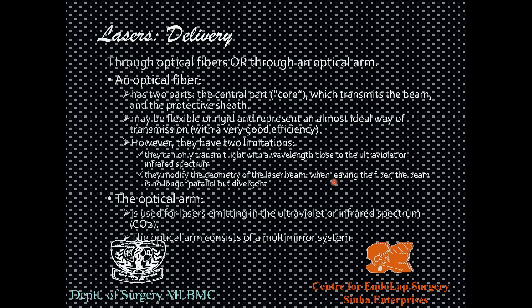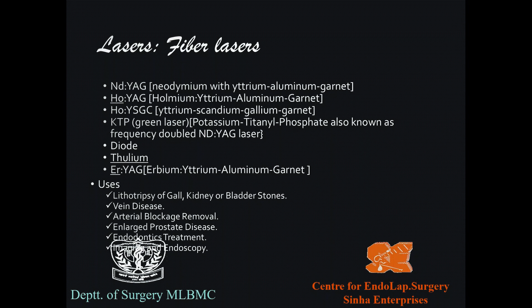The non-divergent, collimated property of the laser beam changes to divergent when transmitted through a fiber. The optical arm, used for lasers emitted in the ultraviolet or infrared spectrum such as the CO₂ laser, is a multi-mirror system that directs the beam onto the target. Common fiber-transmissible lasers include Nd:YAG, holmium:YAG, the yttrium scandium gallium garnet, KTP, diode, thulium, and erbium:YAG lasers.